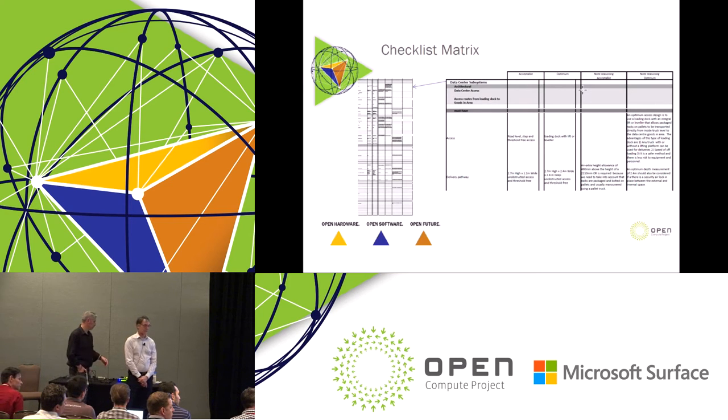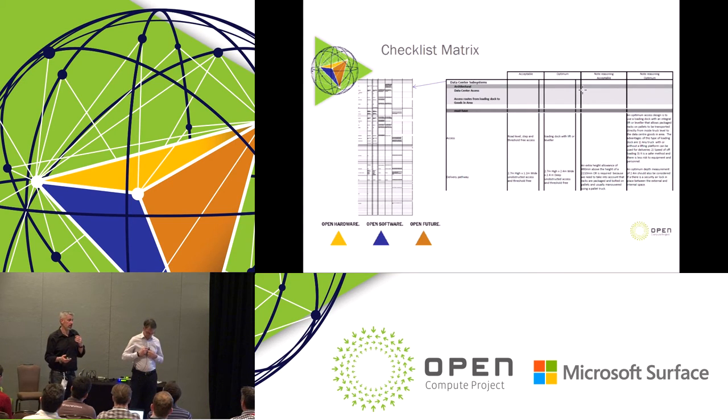Does anyone have any input? The function of the colors is redundancy A and B for network or what is the function of the color? It's not just redundancy, it's all cables. So you can do redundancy cables, your management cables, your crossover cables. So at Fidelity, red and blue for redundancy A and B for redundant paths, black for management, pink for crossovers - a funny story I'll do that offline - phone was gray, and I think that's it for the colors.